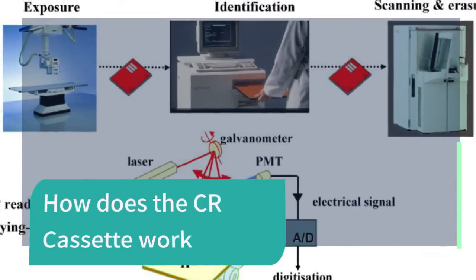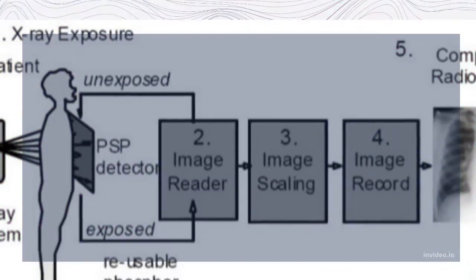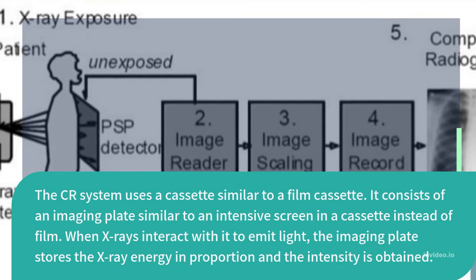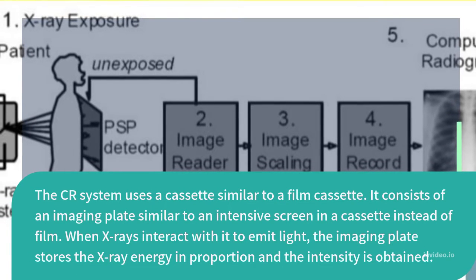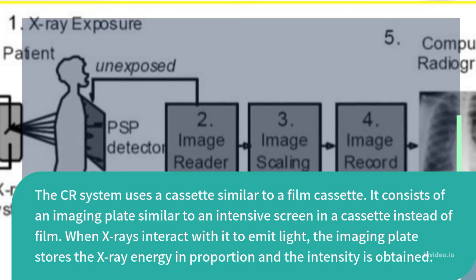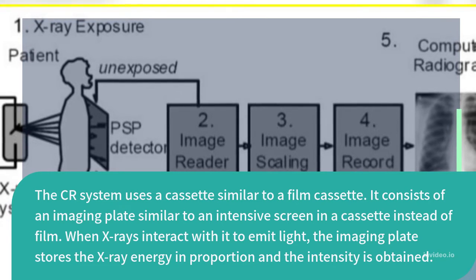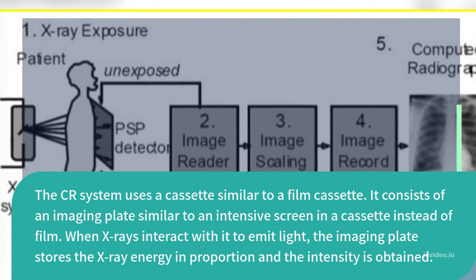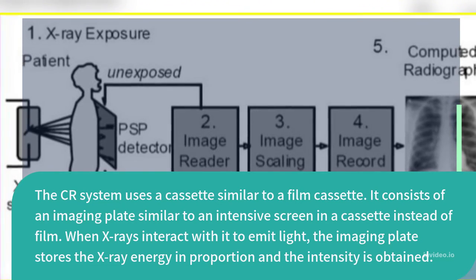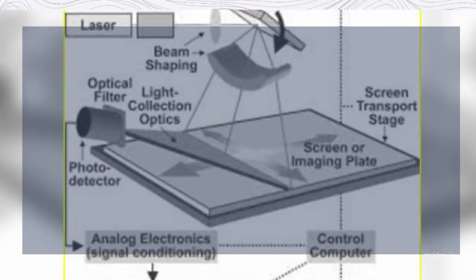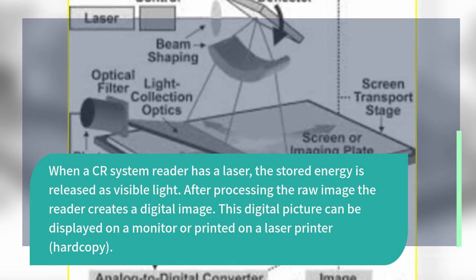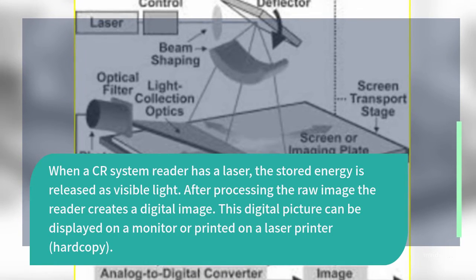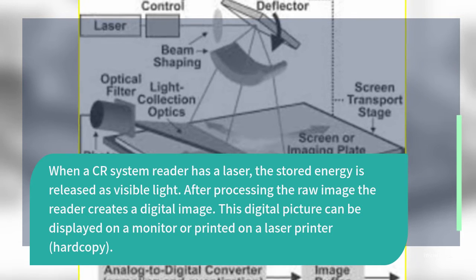How does the CR cassette work? The CR system uses a cassette similar to a film cassette. It consists of an imaging plate similar to an intensifying screen in a cassette instead of film. When X-rays interact with it, the imaging plate stores the X-ray energy in proportion and the intensity is obtained. When a CR system reader uses a laser, the stored energy is released as visible light, and after processing the raw image, the reader creates a digital image.